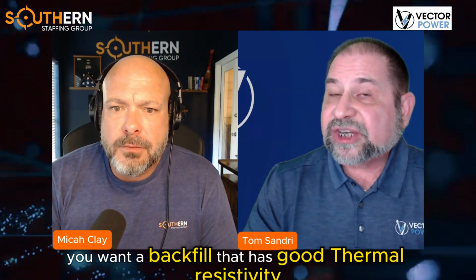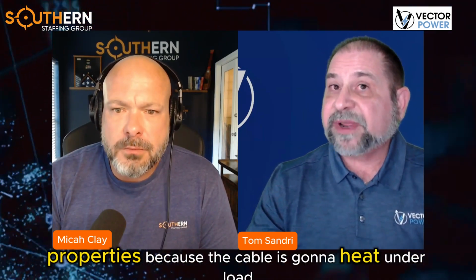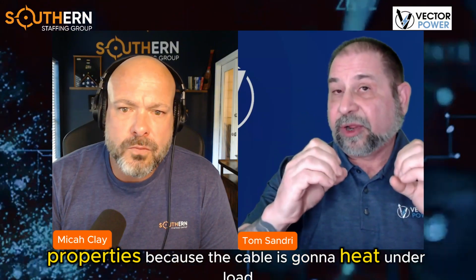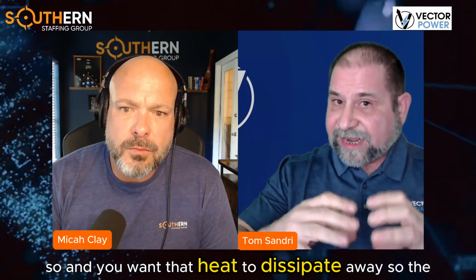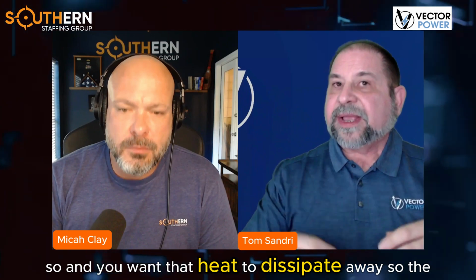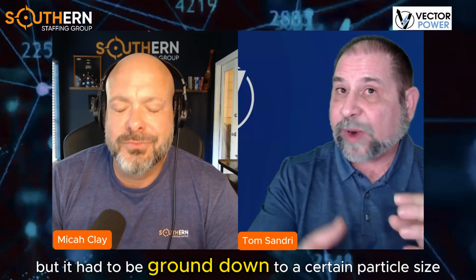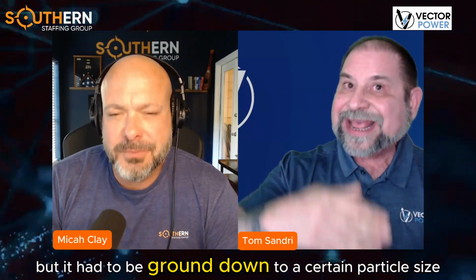So what you want is a backfill that has good thermal resistivity properties, because the cable is going to heat under load, and you want that heat to dissipate away. The design spec basically said that native soil could be used, but it had to be ground down to a certain particle size and compacted to a certain pressure level. Well, this was not done.